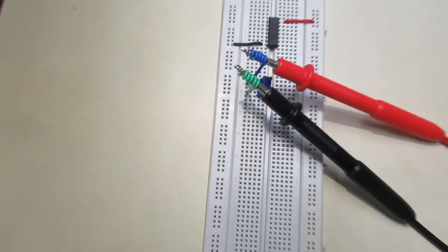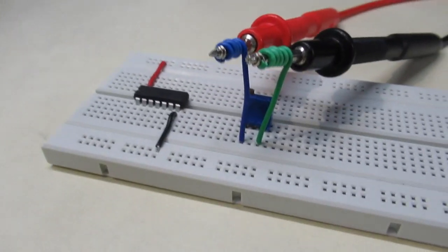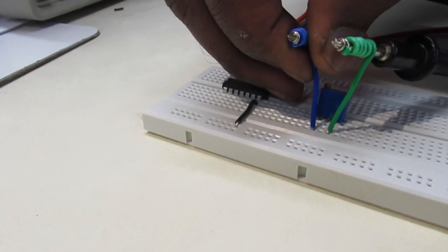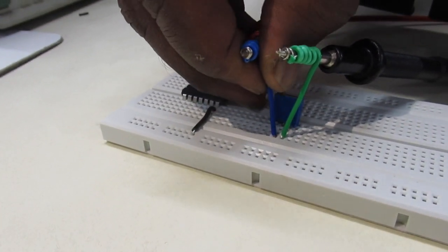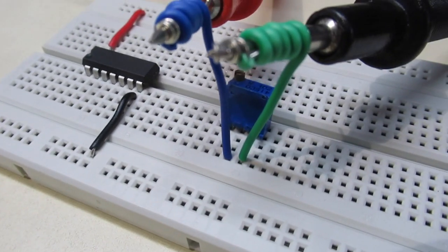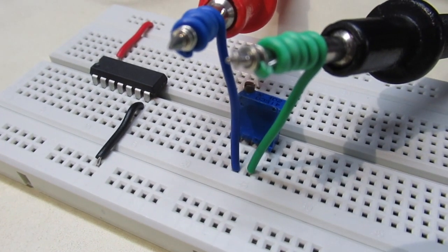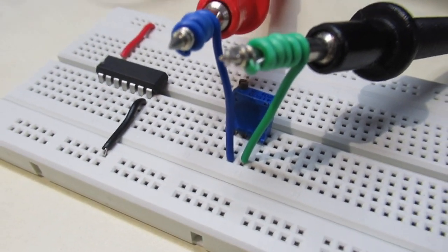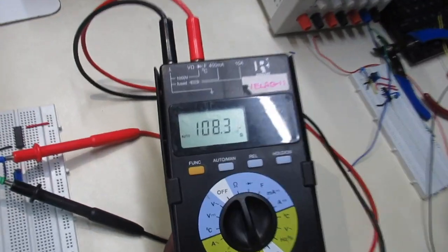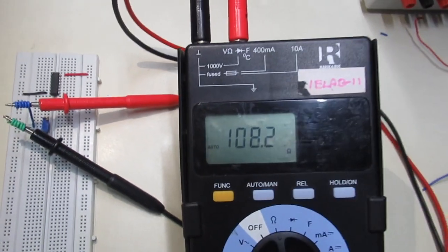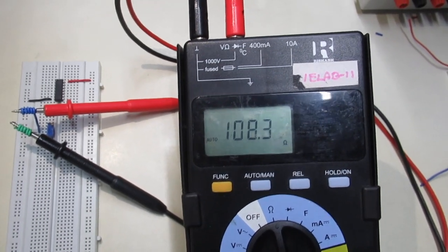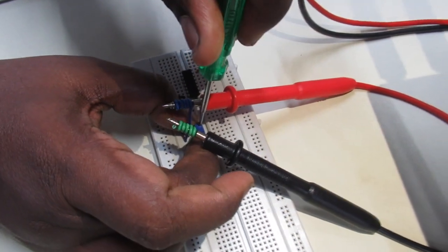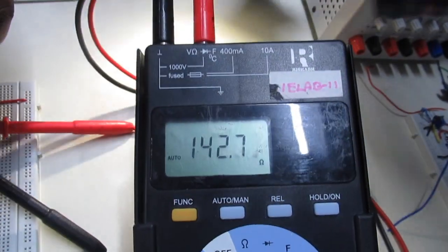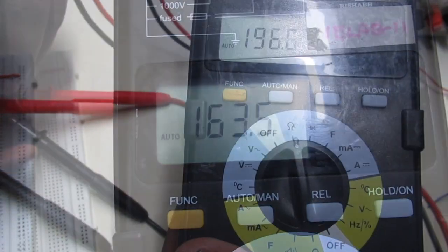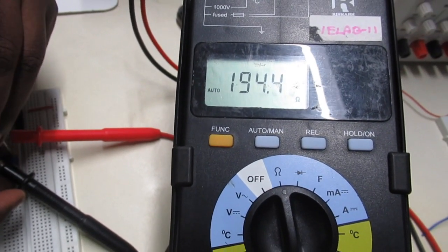We now connect the multimeter between the intermediate terminal and one of the extreme terminals. We move the blue connection to the neighboring pin, connecting the multimeter between the variable resistance and one extreme. Clearly it reads a value of 108 ohms. This value can easily be changed by adjusting the screw: turning it anti-clockwise causes the resistance to go up steadily, and turning it clockwise causes it to come down.